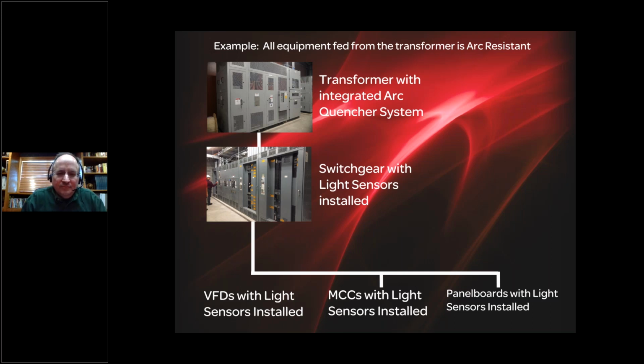Okay, next question that came in. Does Tech4 produce calculations and documentation showing that this switchboard that contains the newly installed light sensors and arc flash relays is now PPE less than 1 and is guaranteed AFIE less than 1.2 calories per centimeter squared? Okay. And the answer is yes, when properly applied and installed.